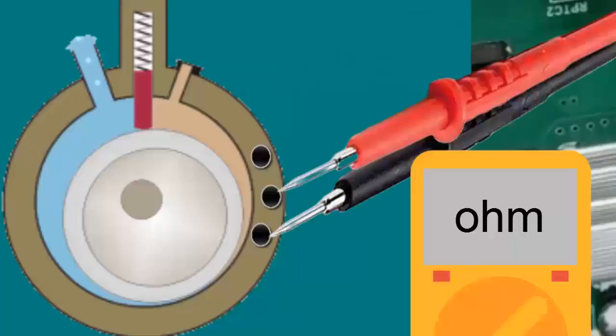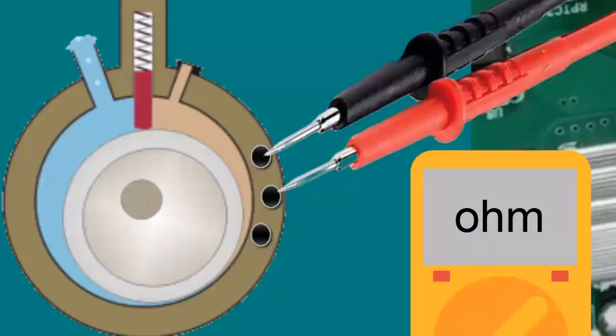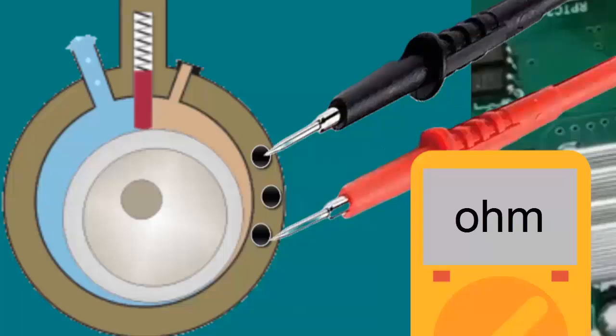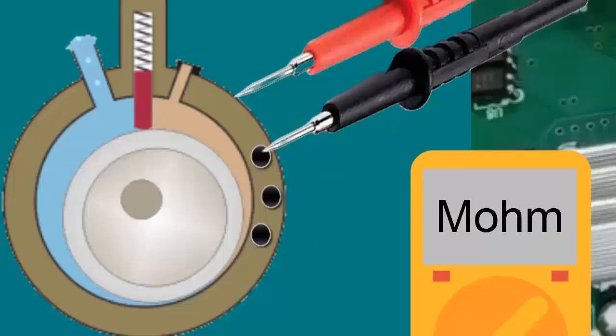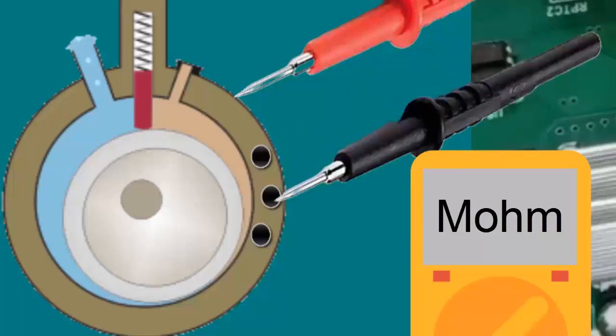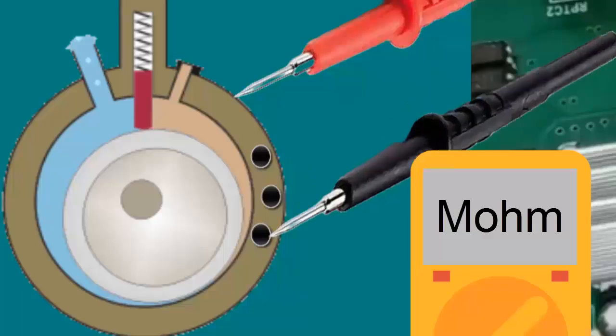4. Disconnect the compressor from the external electronic board. Measure with a multimeter the resistance value between the compressor coils. The ohm values between pairs should be almost equal and never infinite. 5. Ensure there is high resistance between each compressor pin and its casing to rule out current leakage.